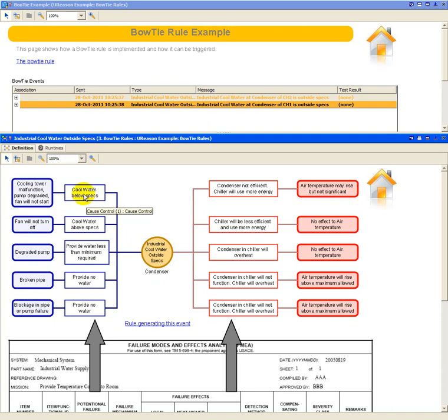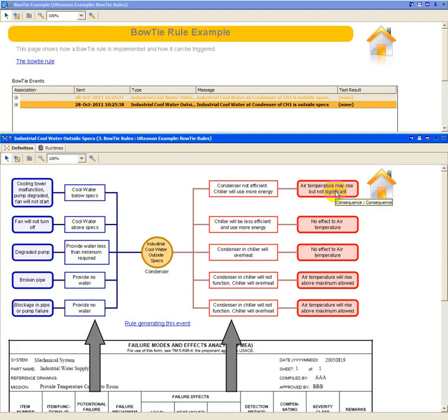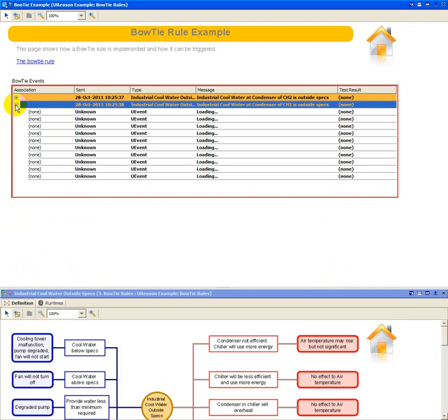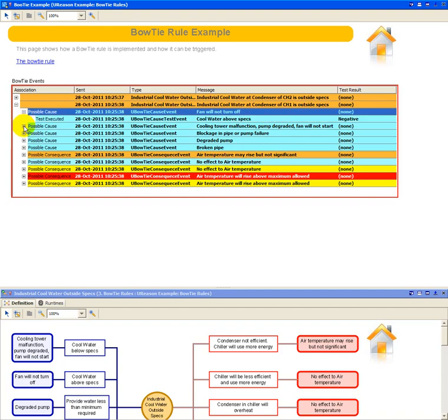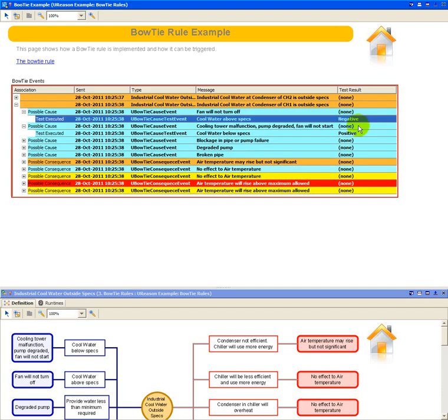So each block here is actually a script that will be evaluated to determine whether this cause is effectively the right cause for this event. And on the right hand side, we have a list of possible consequences, and each of them has a barrier. That is also some code that can be evaluated by this rule to determine whether this consequence is a possible consequence or what is the level or criticality of this consequence. So if I show you an example of that rule now, it has been executed here twice because we have two condensers inside the object model. And as you can see here, under that event, I have a list of subsumed events, a set of subsumed events for the causes, a set of subsumed events for the consequences.